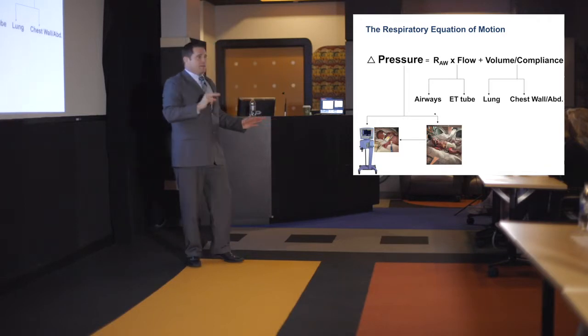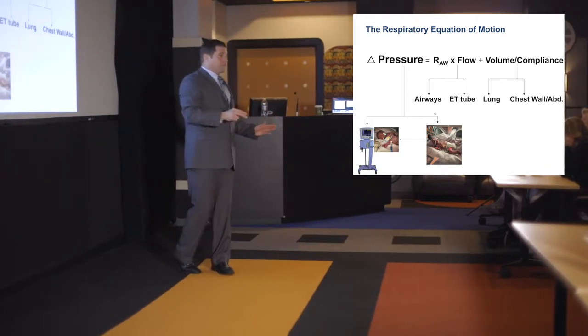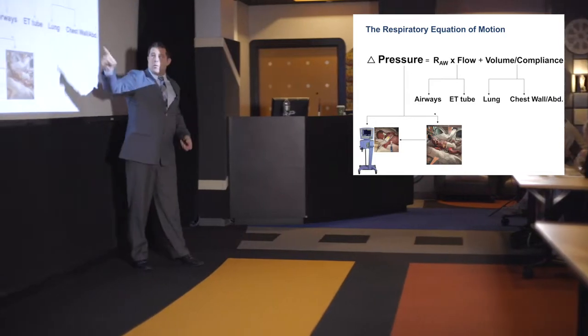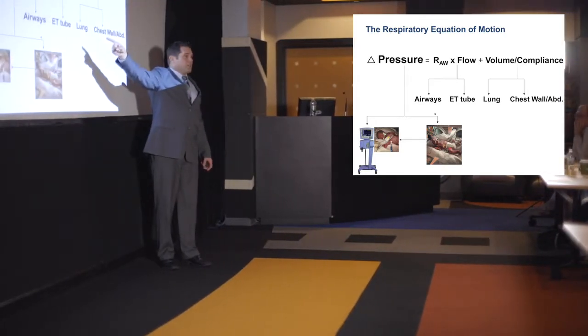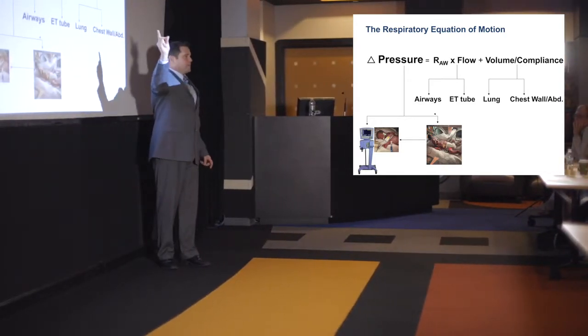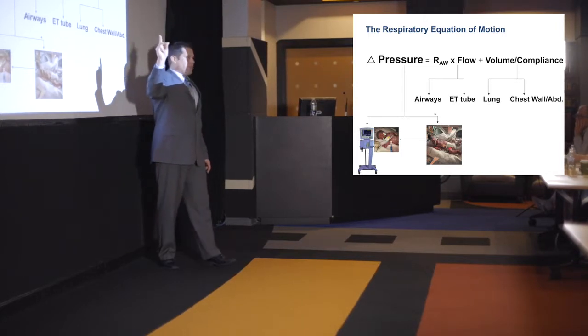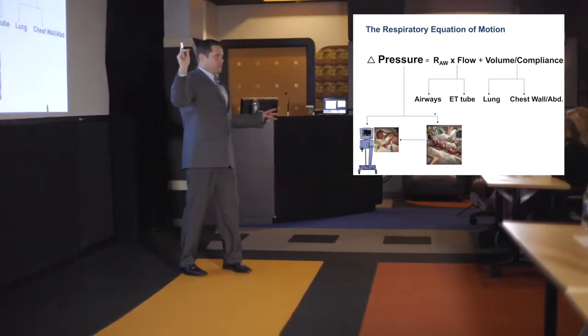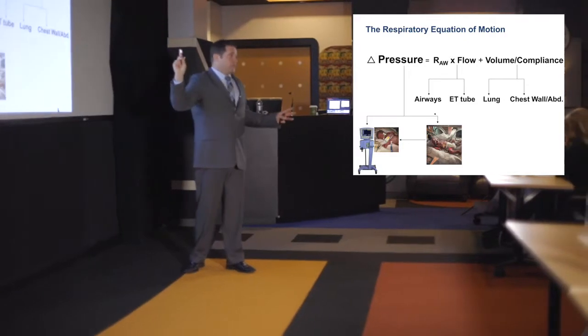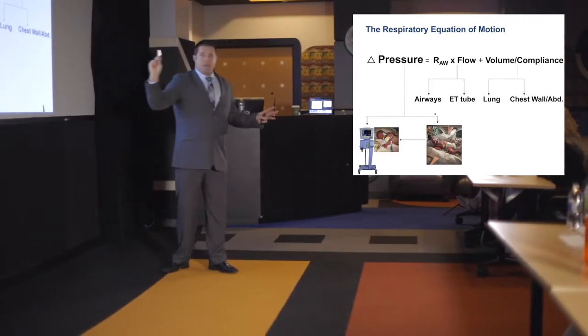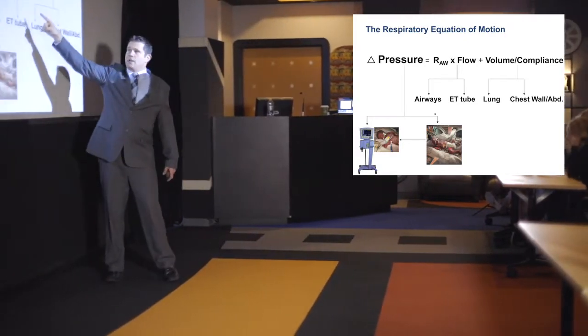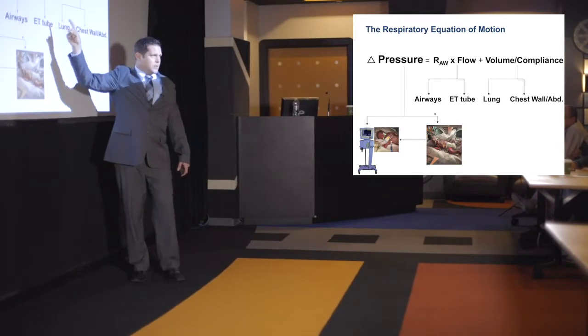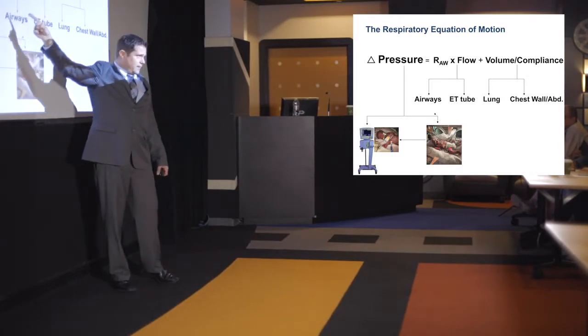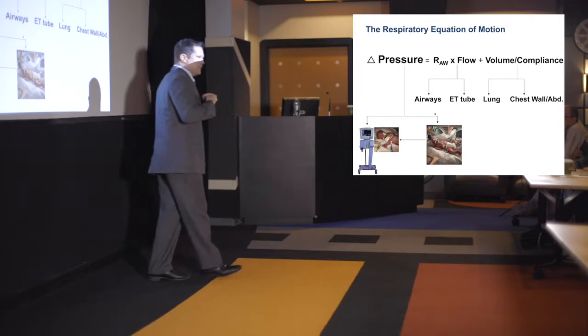Because if you want volume-targeted ventilation to work, you have to realize that the airway pressure does not represent your alveolar pressure. I'm going to say it again. And for people who are still old school, no offense, I was there with you, but it's barotrauma because we couldn't measure tidal volume before. If you have a leaky ET tube and you've got a 50% leak, you have to use a pressure of 30 in order to get a transpulmonary pressure of 15.